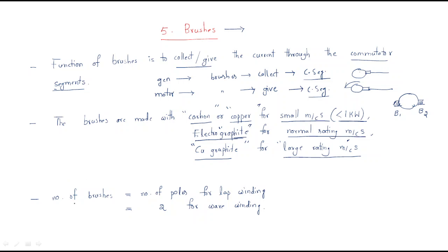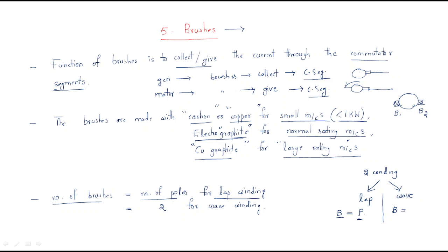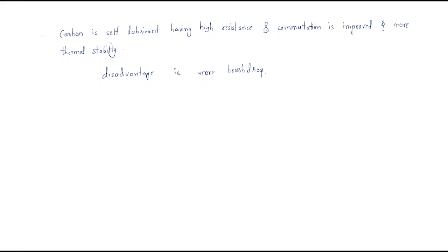The number of brushes is also important. There are two types of winding connections: lap winding and wave winding. For lap winding, the number of brushes equals the number of poles — B equals P. For wave winding, the number of brushes equals two.